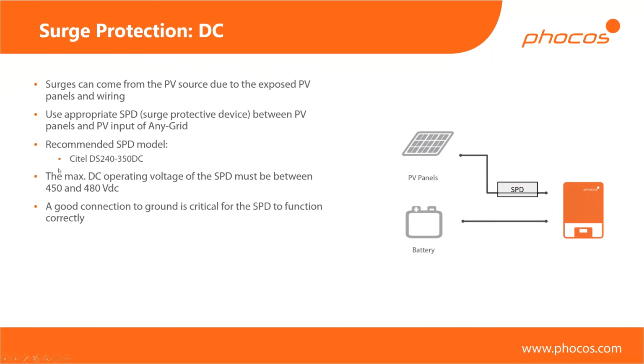And then for the PV side, we recommend this model. It's very important to have the correct rating for the SPD coming from PV, because a lot of people make the mistake of thinking they can use any old SPD that they use for a grid-connected inverter, where a lot of these will only start protecting for voltages above 1,000 volts. This inverter already has a very high maximum PV input voltage of 450 volts. But if you connect an SPD which only starts protecting above 1,000 volts, that's a difference of over 500 volts. It's not going to do any protecting, because if the voltage rises to, let's say, 800 or 900 volts, the SPD is still not doing anything, and the inverter is already taking damage. So if you do install an SPD, which I recommend, make sure you take the right one, because otherwise it will not do its job of protecting from high voltage peaks.